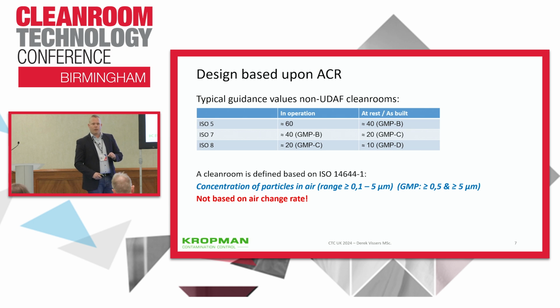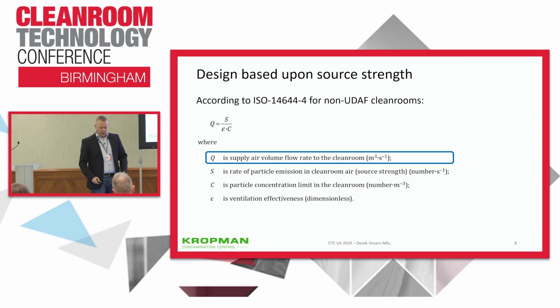And of course I understand that for decades this worked quite well when sustainability was not an issue. But I think now we have to use another approach. The new ISO standard on design, construction and startup, part 4, gives a straightforward equation, which is quite easy to fill in, to calculate how much air is required based on the estimation of the particle emission in your clean room and the ventilation effectiveness.